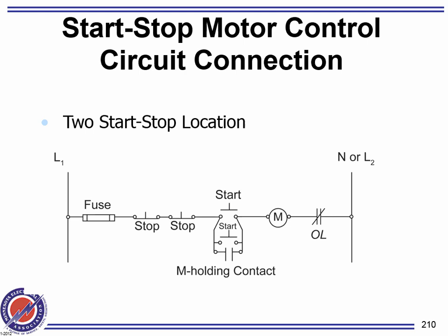Okay, for this one, guys, you must always series the stops and you shall always parallel the start. That's a rule. Series the stop, parallel the start. And the holding contact must always be across what? The start.